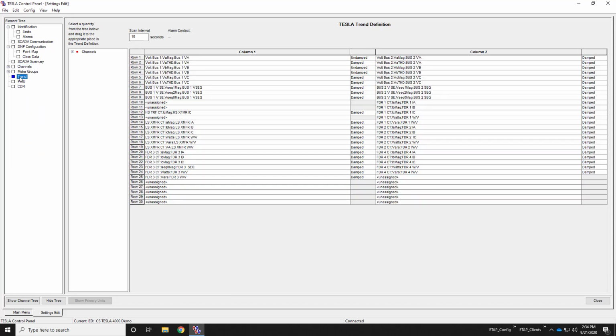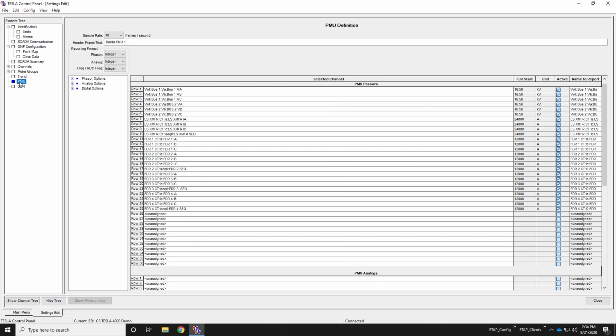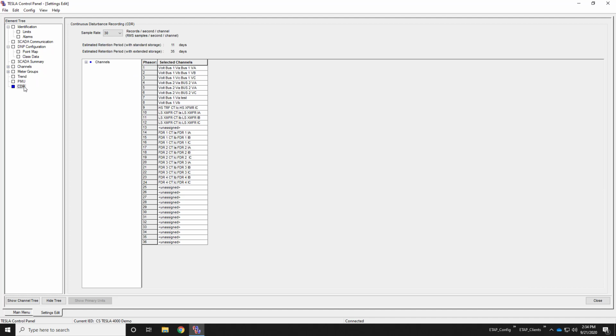Additionally, in the trend section, you can define what measurements you'd like to trend and make available for a ComTrade file. Here you can define what measurements are used for the PMU data, so what do we want on our phasor data available? Finally, the CDR is our continuous disturbance recording capability, where we can continuously create those ComTrade type files and make that available on a running basis. So next, I'm going to leave the settings mode and go back to my main mode.